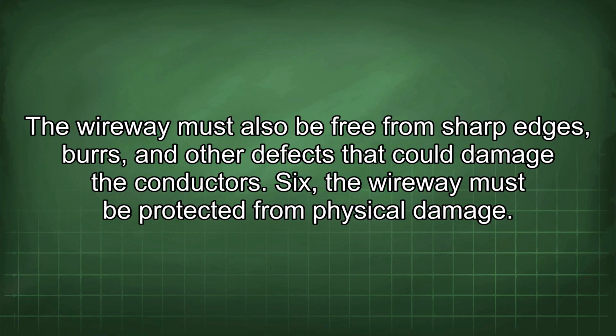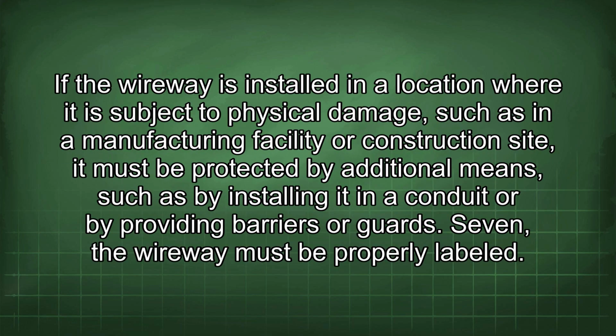6. The wireway must be protected from physical damage. If the wireway is installed in a location where it is subject to physical damage, such as in a manufacturing facility or construction site, it must be protected by additional means, such as by installing it in a conduit or by providing barriers or guards.